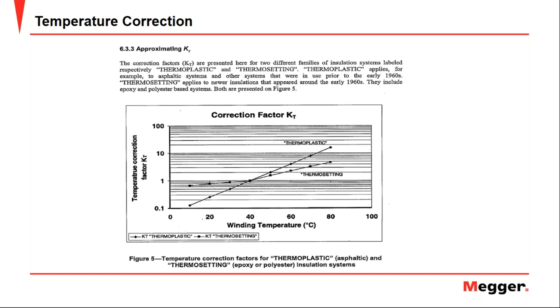Now, let me give you some temperature tips. When the motor is heated in an oven or by any external means, such as lamps, for example, the winding temperature will be very similar to the motor case temperature. But if the motor has been running, and of course it is hot, and we measure the temperature on the motor case, the winding temperature will be that reading plus 10 degrees Celsius approximately. This is not in the standard, this is just a rule of thumb.